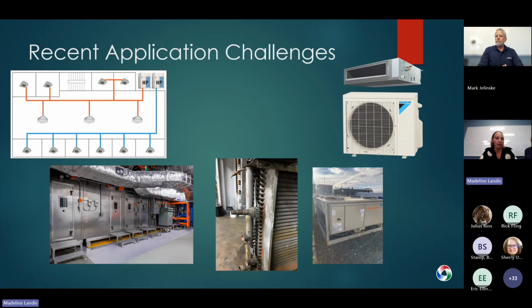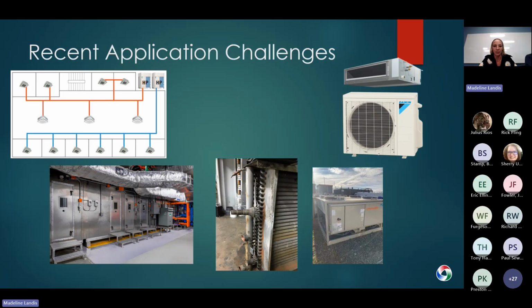So some application challenges that we have experienced during both design and installation with these new refrigerants and the slight risk of flame propagation is that there's additional measures that must be taken during VRV design, during indoor air handling unit with a split DX condenser design, and even with indoor water-cooled chillers, there's things that you just need to pay attention to that previously you didn't. You want to take careful consideration to the installation location. You want to make sure that the refrigerant charges in those spaces is going to be below a certain level. So there's just some challenges that we've seen that all of you, I'm sure, are experiencing with retrofits and new designs.